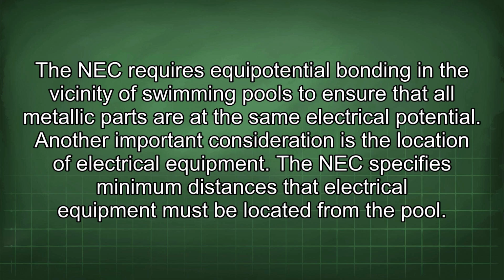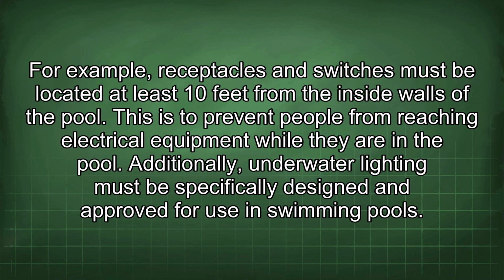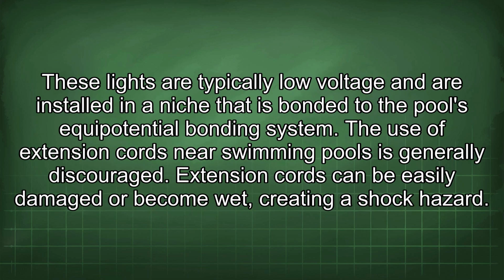Another important consideration is the location of electrical equipment. The NEC specifies minimum distances that electrical equipment must be located from the pool. For example, receptacles and switches must be located at least 10 feet from the inside walls of the pool. This is to prevent people from reaching electrical equipment while they are in the pool. Additionally, underwater lighting must be specifically designed and approved for use in swimming pools. These lights are typically low voltage and are installed in a niche that is bonded to the pool's equipotential bonding system.